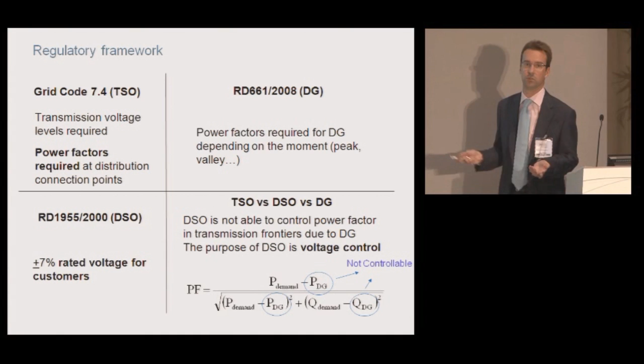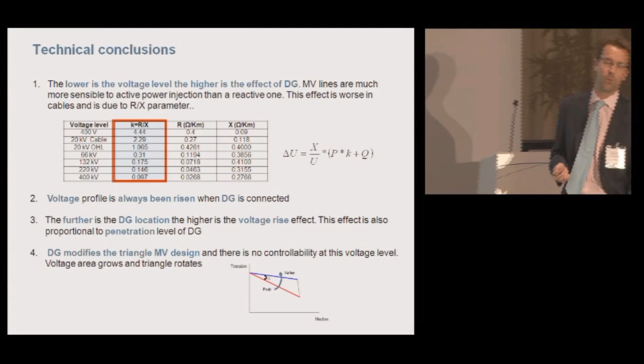Conclusions and proposals. Technical conclusions. It's very important the relation between the resistance and the reactance, because this parameter is telling us that the active power is the main driver for voltage control in medium voltage and low voltage grids. Also, this parameter is much more significant in cables than in overhead lines. That should be considered. Voltage profile is always being raised when we are connecting distributed generation into the grid. The farther the distributed generation is from the feeder, the higher is going to be the effect in terms of voltage rise.